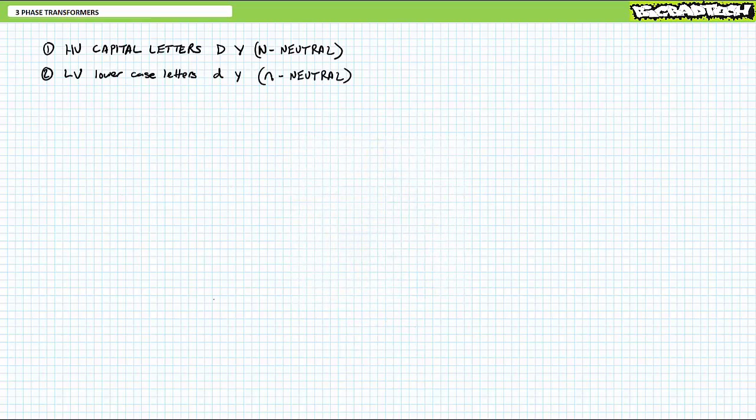Anyways, part 2 is the configuration of the low voltage side. Y or delta using lowercase letters, Y or D. Similar prohibitions exist on using the looser term star for clearly Y-connected low voltage windings. Additionally, if the high voltage or low voltage side, when configured as a Y, not a star, has a fourth neutral line, it'll indicate it with an N. Again, capital letters for the high voltage side and lowercase letters for the low voltage side. Additionally, you might run across a Z or a zigzag connection, which I'll explain later, or maybe not at all.